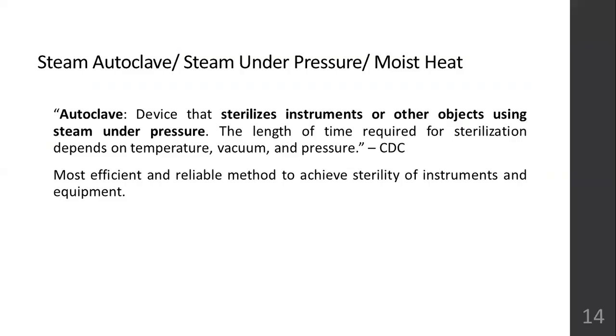So in the steam autoclave method or steam sterilization method, moist heat is used and steam under pressure is used. This device sterilizes the instruments or other objects using steam under pressure. And the length of time required depends on the temperature, vacuum, and pressure. Higher the pressure, higher the temperature, less amount of time. But if the temperature is low and the pressure is low, the time spent by the instrument for sterilization is higher. And this is one of the most efficient and most reliable methods of achieving sterility.